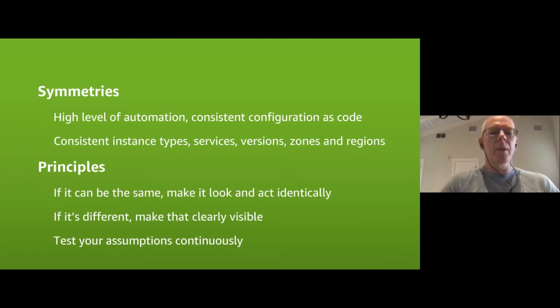So here's the principles. If it can be the same, make it look and act identically. Be careful to not introduce things to break the symmetry. Just maybe for, well, I don't really need two of these, so I'm going to optimize and make this one a little bit different. It's actually, from a resilience point of view, good to have them both be the same.